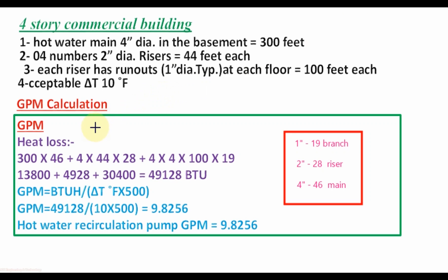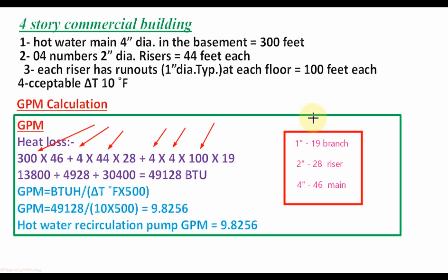The 4 inch diameter pipe at the basement is 300 feet. Each of the 4 risers is 44 feet at 2 inch diameter. There are 4 branches per riser, 16 branches total, each 100 feet at 1 inch diameter. Applying the heat loss rates — 19 BTU/hr/ft for 1 inch, 28 for 2 inch, and 46 for 4 inch — and multiplying by piping lengths, the total heat loss in the hot water supply piping equals 49,128 BTU per hour.